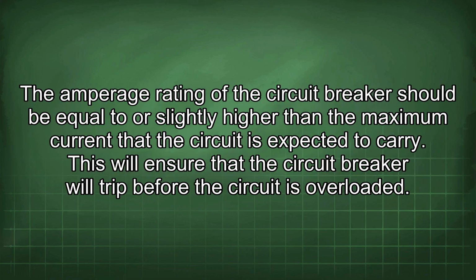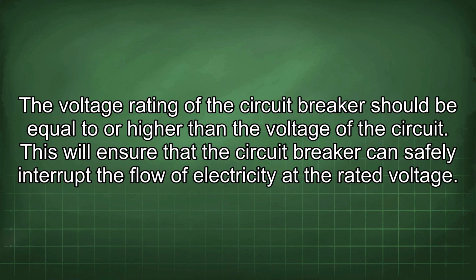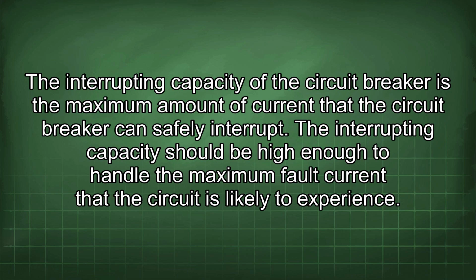The amperage rating of the circuit breaker should be equal to or slightly higher than the maximum current that the circuit is expected to carry. This will ensure that the circuit breaker will trip before the circuit is overloaded. The voltage rating of the circuit breaker should be equal to or higher than the voltage of the circuit. This will ensure that the circuit breaker can safely interrupt the flow of electricity at the rated voltage. The interrupting capacity of the circuit breaker is the maximum amount of current that the circuit breaker can safely interrupt. The interrupting capacity should be high enough to handle the maximum fault current that the circuit is likely to experience.